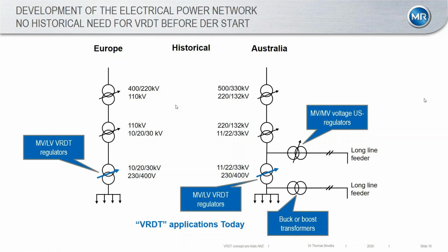With voltage regulated distribution transformers, or tap changers in general, both the MV and LV level transformers can now be regulated. That's a big step forward in taking care of voltage from an asset that is also owned and can be controlled by the network operator.